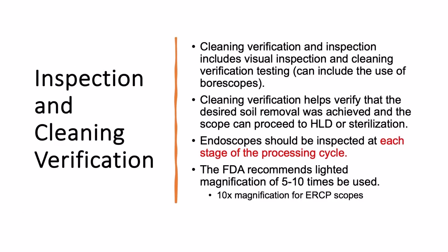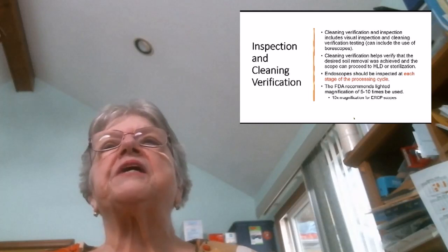Cleaning verification and inspection includes visual inspection and cleaning verification tests, and this can include the use of a borescope. Again, from a legal perspective, I think the borescope is the best thing that can happen because it'll take a picture and it's a documented record of what went on inside of that scope. Remember, cleaning effectiveness is going to look for soils, whereas a borescope will not only look for soils, but it'll also look for objects. Cleaning verification helps to verify that the desired soil removal was achieved, and the scope can then proceed to high-level disinfection or sterilization.